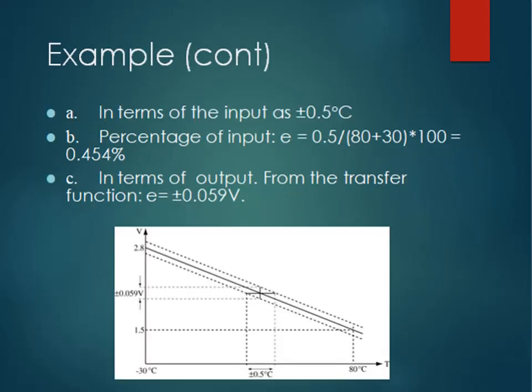In terms of the input, as plus minus 0.5 degrees Celsius, the percentage of input E is equal to 0.5 divided by (80 plus 30) into 100, that is equal to 0.454%. So in terms of output from the transfer function, E will be equal to plus minus 0.059 volt. Here you can see for that particular span how from the transfer function we can calculate E, which is equal to plus minus 0.059 volt.